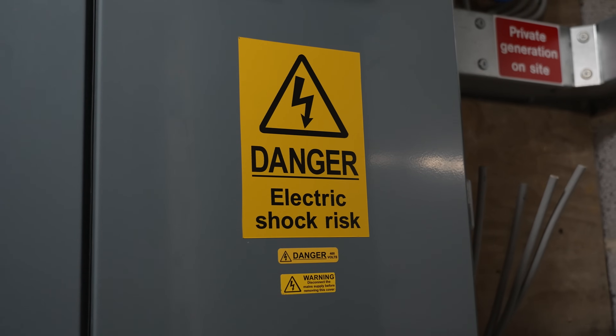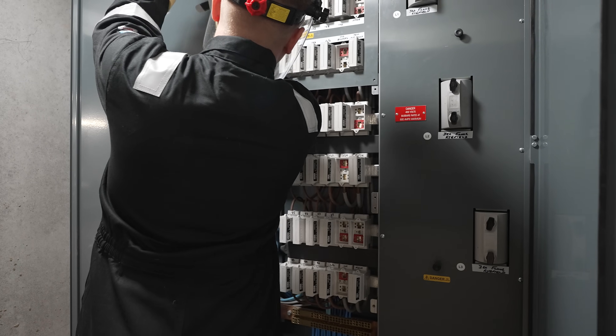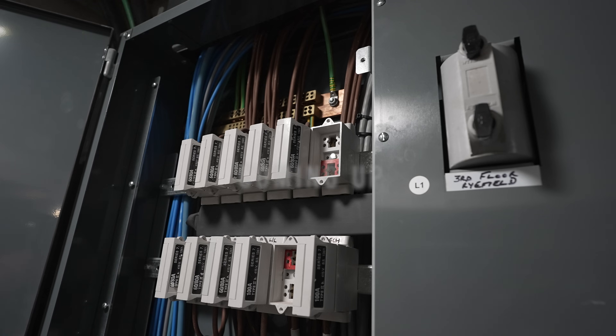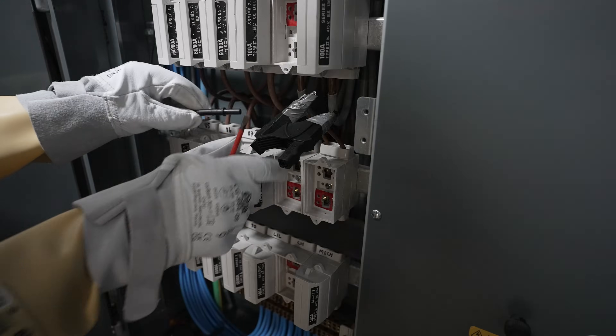We're back today and we are data logging a four-story building. The reason we're doing that is because there's been a dispute over the service charge, the general electricity charge of the building. We're going to be logging the data with these PEL104s, which is essentially going to give you your power factor.